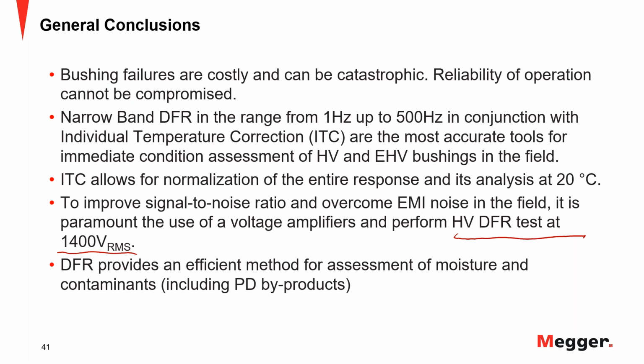And of course, remember that the DFR provides an efficient method to assess moisture and contaminants, including PD byproducts. And this is one interesting thing, that sometimes you may see a high level of moisture, but especially when we talk about bushings, it might be related to contaminants, right? And type of contaminants, especially we have seen X-wax to give a very similar dielectric behavior as it does moisture in the system. So just that for you to keep in mind.